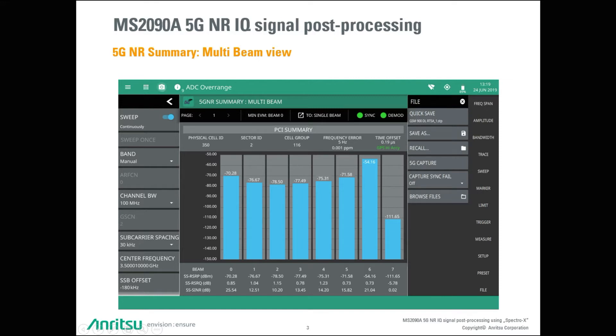In order to initiate an IQ capture of such a 5G new radio signal, you just enter the MS-2090A file menu and tap on the button 5G capture. This operation takes a 40 milliseconds lasting time record of IQ data which is finally saved into the internal memory.